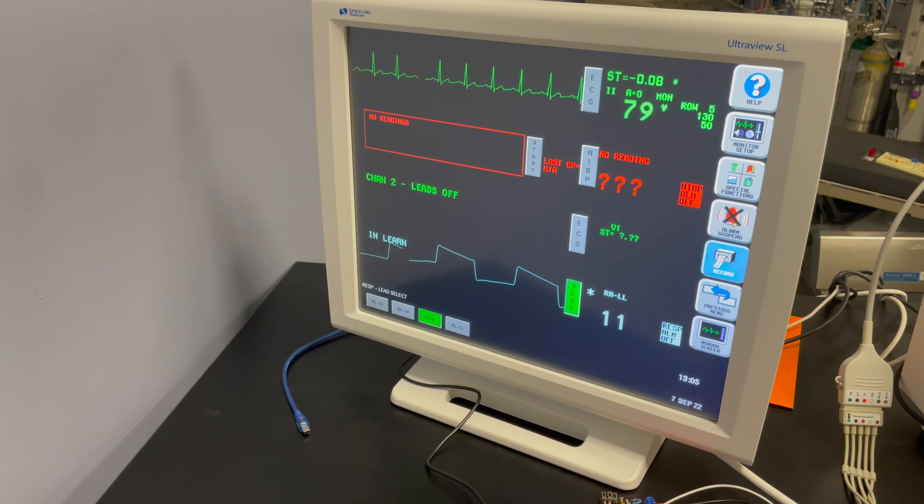Now different devices choose different leads to default to. Some Spacelabs monitors like this one don't default to RA-LL, but if you use the cubes they do default to RA-LL. It just depends on what type of patient monitor you're using, but most of the times you're able to go into the settings and select the correct leads.